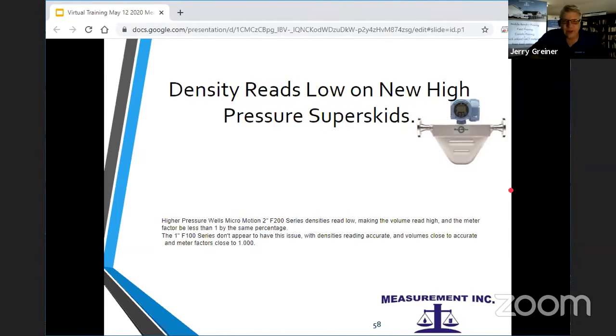Okay, just a couple more things. There are these new Superskids, and I must have thought that you guys could read really, really small writing when I wrote this one here. They have a 2-inch Coriolis meter on these new high volume wells that we are looking after. On the 2-inch F series, we found the densities were reading consistently low, making the volume read high and the meter factor less than 1 by that same amount.